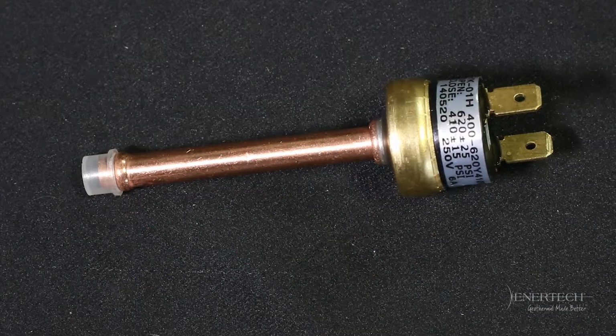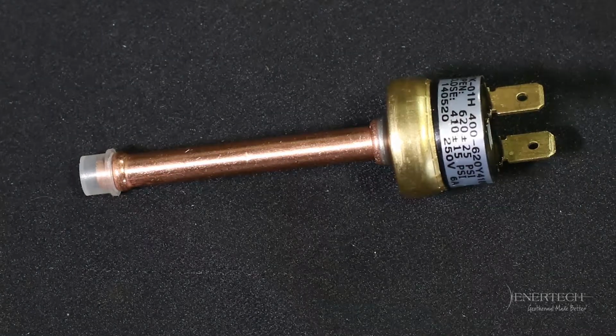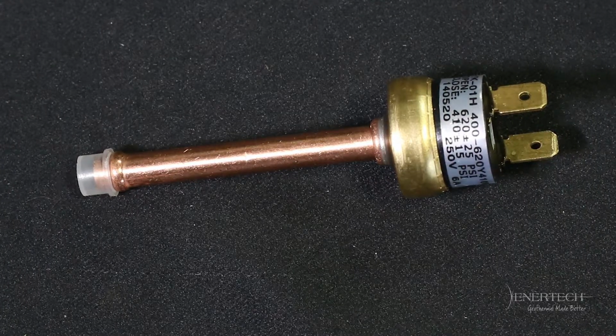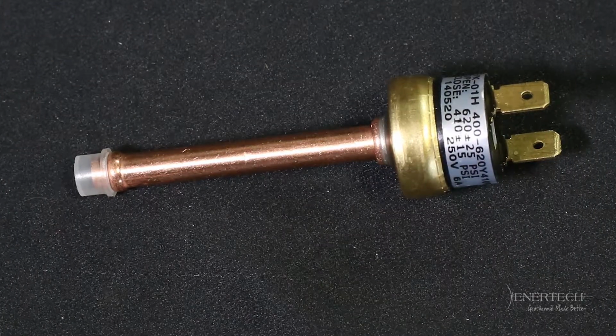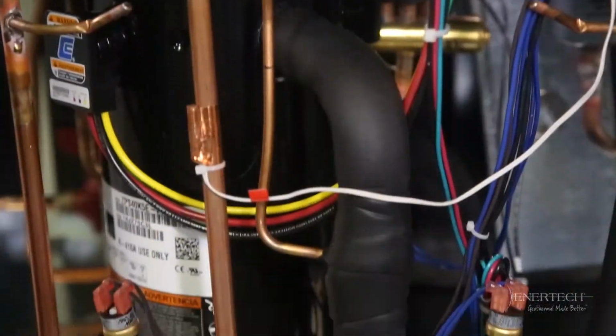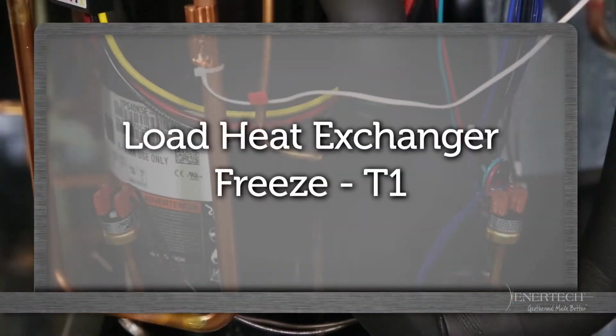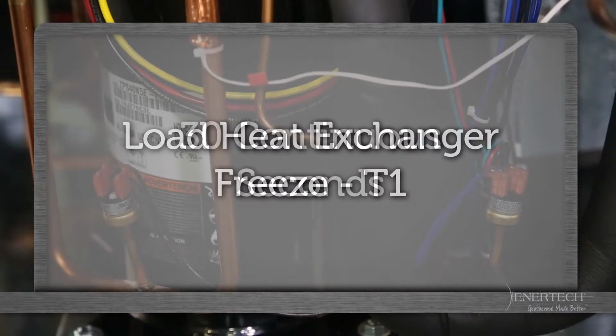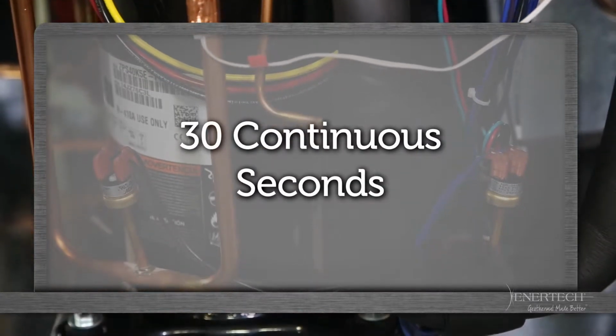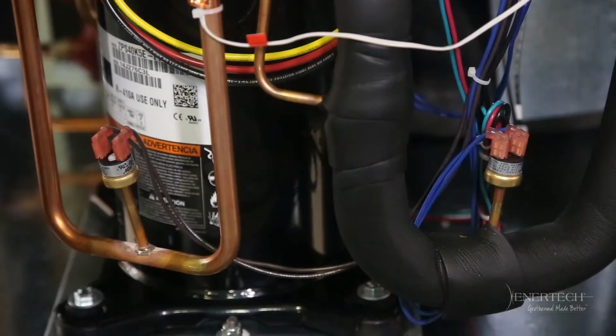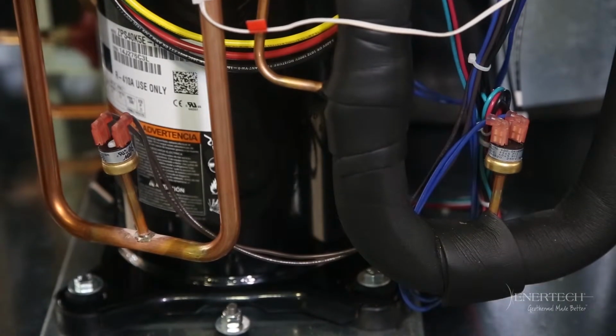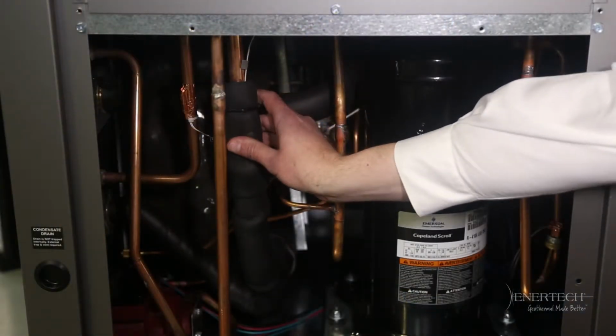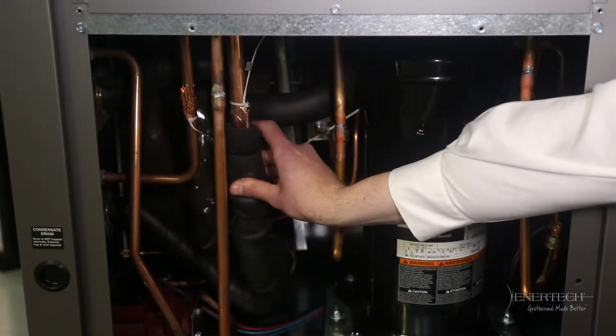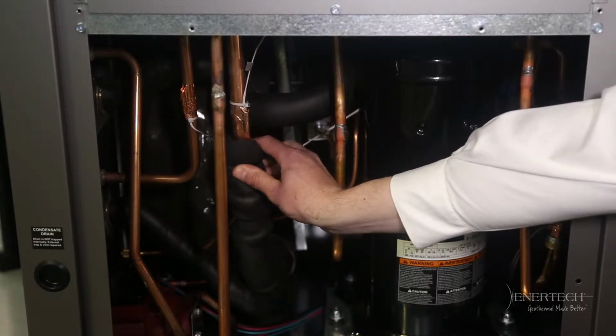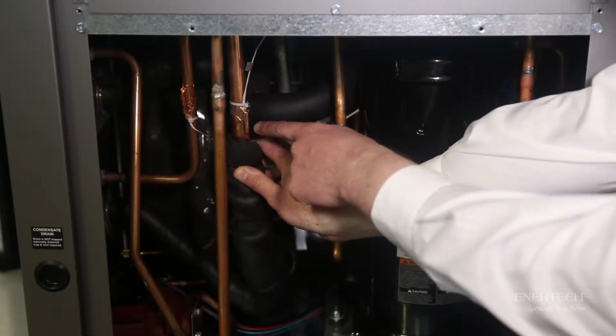Note, if the high pressure switch is open before startup, then the unit will not start upon receiving any Y1 call and will lock out instead. When in cooling mode, if the load heat exchanger temperature is lower than 30 degrees for 30 continuous seconds, the compressor operation will be interrupted and the control will go into fault retry mode. The sensor is located on the refrigerant line in between the heat exchanger and TXV, the refrigerant inlet of the heat exchanger in cooling mode.